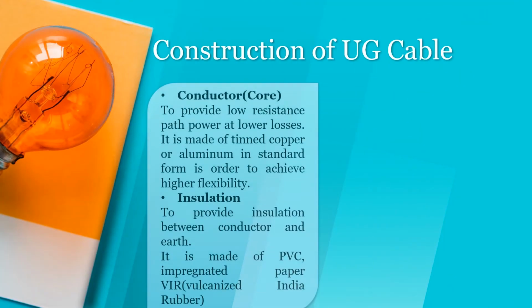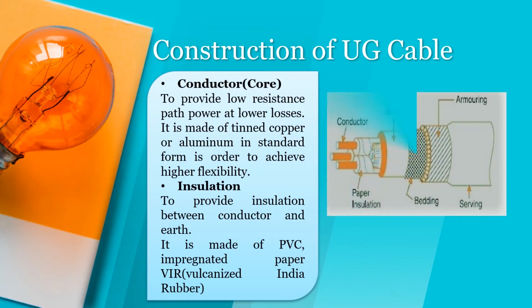Construction of UG cable. Conductor: provides a low resistance path for power at lower losses. It is made of tinned copper or aluminum in standard form in order to achieve higher flexibility. Insulation: provides insulation between conductor and earth. It is made of PVC, impregnated paper, VIR, vulcanized Indian rubber.